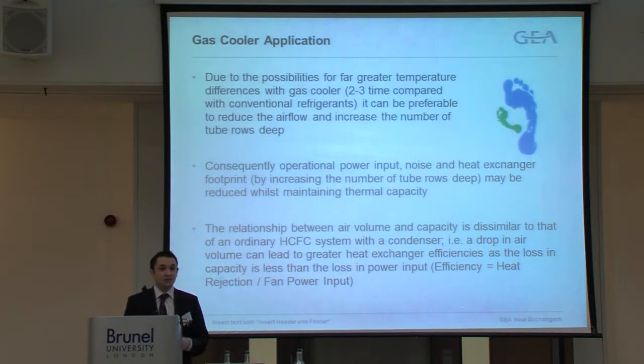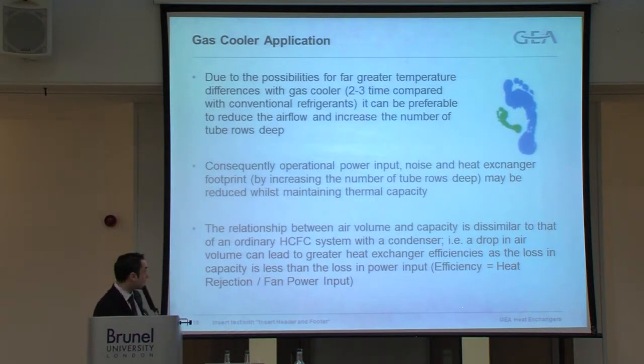So the total carbon footprint within the supply chain is reduced for the end users, as well as the energy efficiency in operation. The relationship between air volume and capacity is also dissimilar to that of a conventional HCFC. For a conventional system, if you were to increase the air volume by, say, 50%, that would increase the capacity potentially by 25%. This isn't the case with a gas cooler. We know that that relationship is actually quite different, and you will see the end use of that out of our selection program.